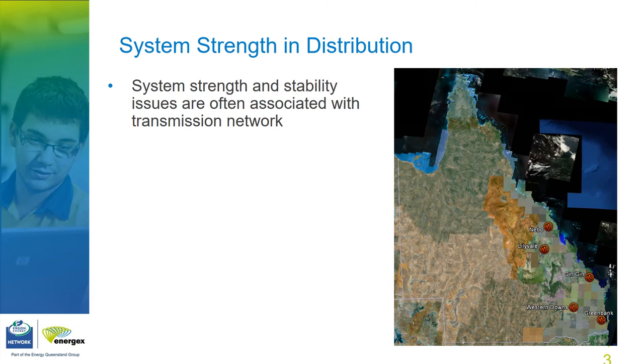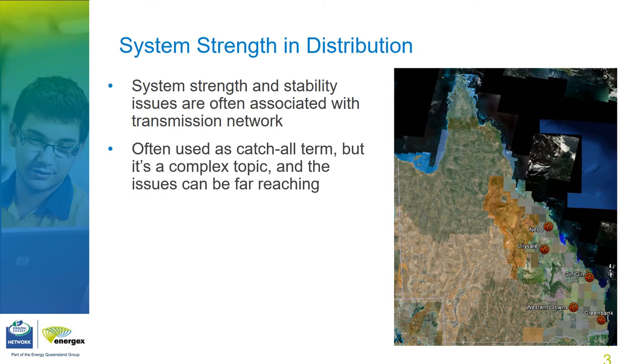So historically, the terms system strength and stability are often associated with the transmission network. And we see that through our connections experiences, where it's often assumed that the connection to a distribution network is less onerous than the transmission. In many cases, this is not true. And the experiences with the TNSP connections do not always translate to experiences with the DNSP connections. We find that system strength and stability are often used as a catch-all term for the broad issues, but the issues are often complex and far-reaching.